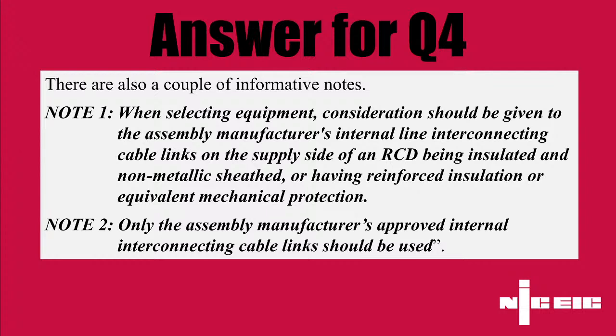So yeah, it's possible. And I was always taught about the fact that we don't really want that upfront RCD, because effectively that can create your single point of failure. And if you look at division of installation, that tells us we should try and minimise that. Obviously, there are some instances where you can't avoid it, but where you can, and this would be a good one, you could avoid it by having double insulated tails.